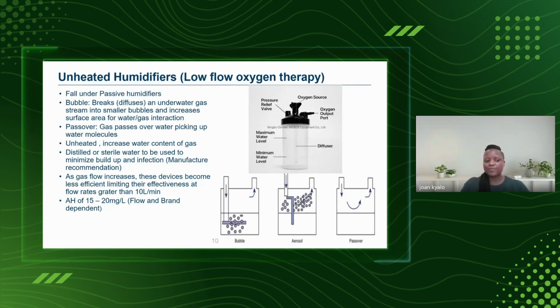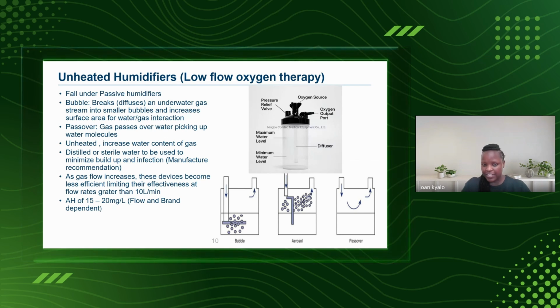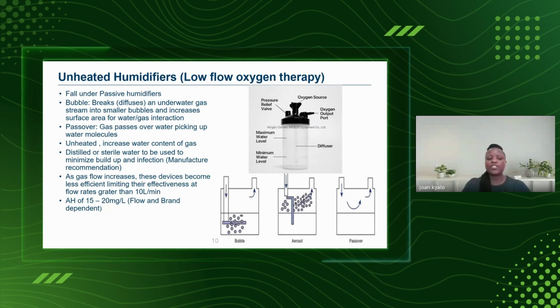And also we know this is flow dependent, because as gas flow increases, the ability of the diffuser to break it up, and really for the gas to interact with the water, decreases. So that means at 15 liters of flow, you will not be able to get to 20. But at 10 liters or 8 liters, you are able to get at least to 20 milligrams. And this is also very dependent on brand, but also the lower the flow, the higher the chances that you'll have a little bit more humidity. But the maximum it can give you is about 15 to 20.